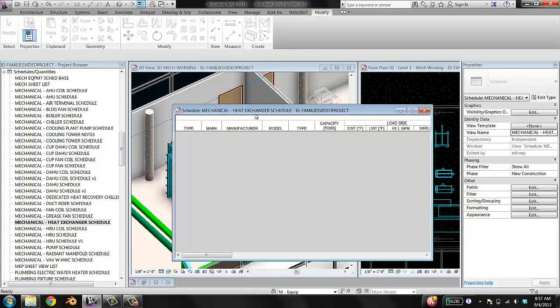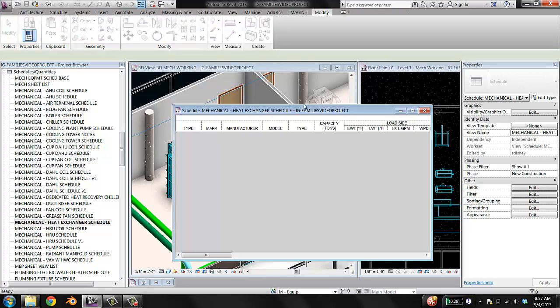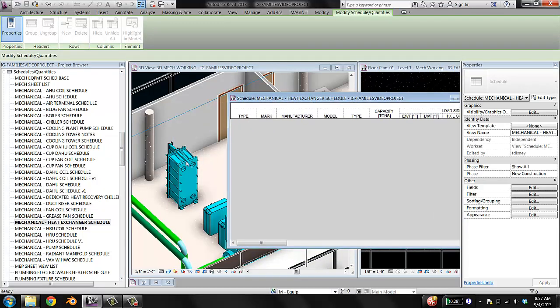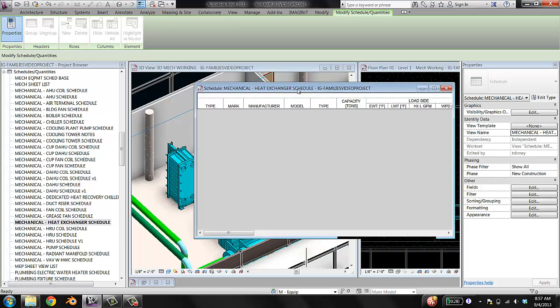Go ahead and open it up. You can see that even though we have a heat exchanger family in the project, it's not populating the schedule. The reason for that is that each of these schedules is set to filter mechanical equipment families based on the Type Mark parameter, because we don't want every single piece of mechanical equipment to show up in this list — we just want the heat exchangers.